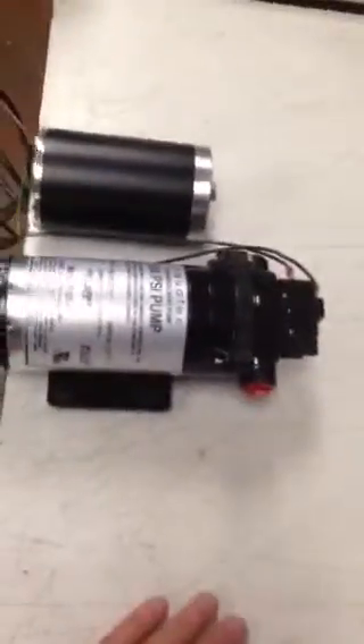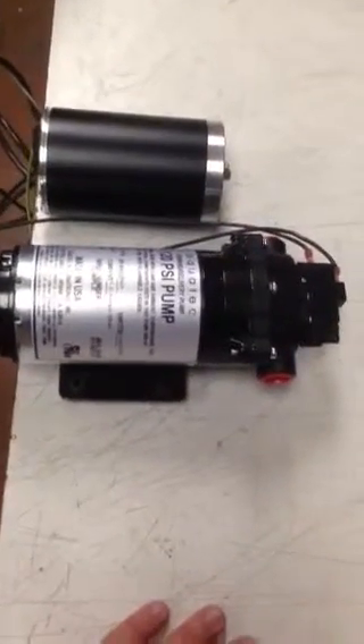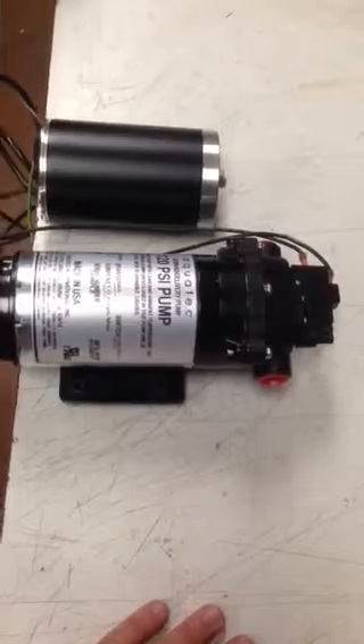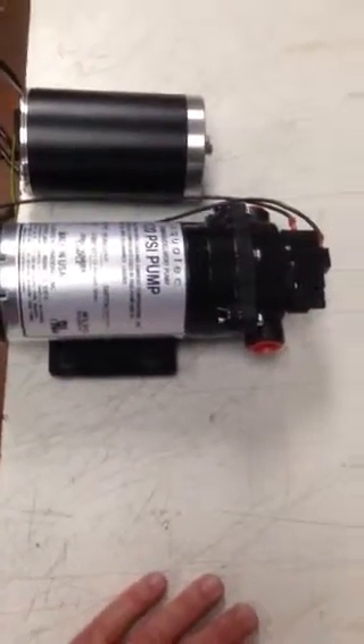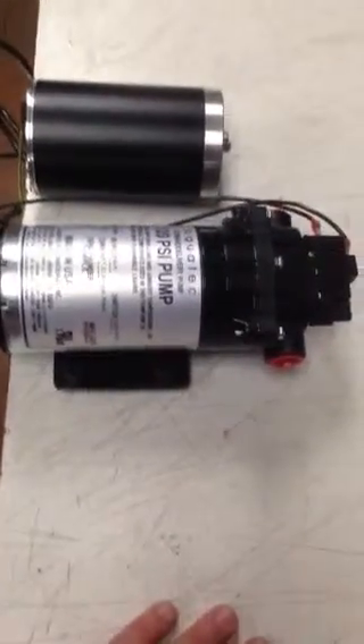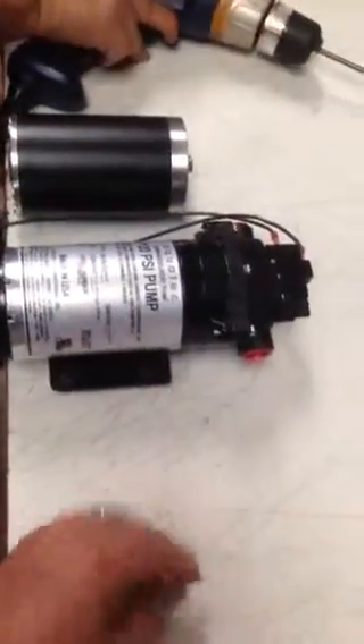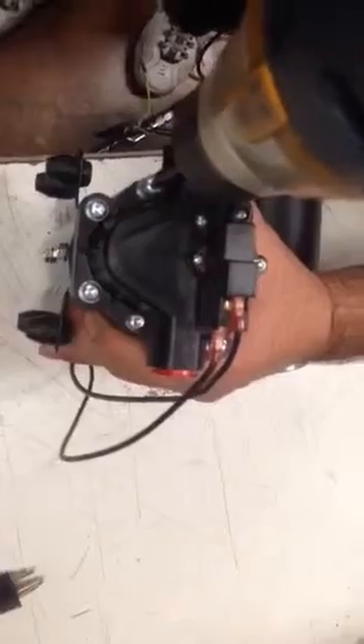We use Torx fasteners because they do what they're supposed to do, which is transfer the full torque of the driver into the fastener into the head for maximum grip and fastening. So first we take the pump head off of the previous motor by removing three of the fasteners that hold the pump head to the motor. These fasteners are going to have a lock nut washer and a little washer, so you just pull them out in the same order. You pull them out in order.